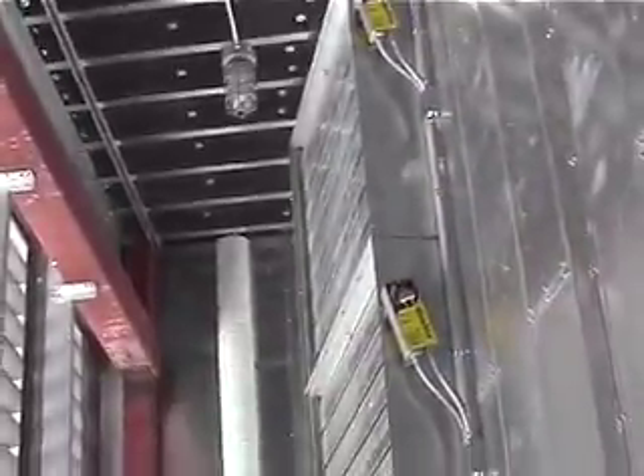We've got our outside air intake section right here. So this damper section here is for your outside air fan, which, like I mentioned before, only opens when we're below 44 degrees outside. And then this section here is your regular outside air damper intake. Mounted on the outside of that section is your airflow station for that damper section. And this ties back to that panel, that white enclosure I showed you on the other side of the unit.